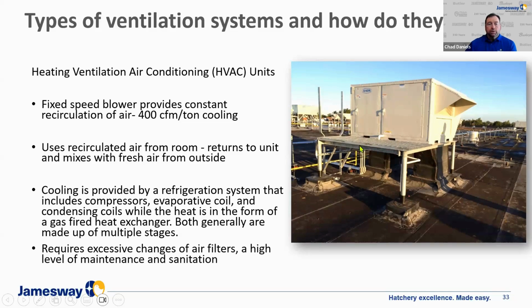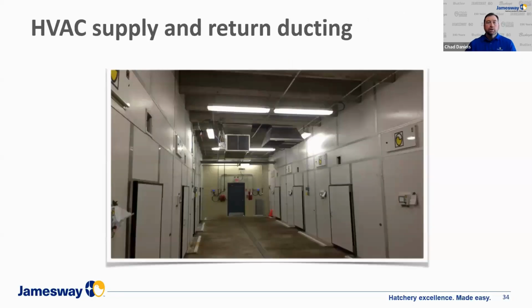So with a system like this, we see it requires excessive changes of air filters. It has a high level of maintenance. It also has a high level of sanitation, because some of the dirtiest air we have in the hatchery comes from our egg pack. And anytime we're pulling that air from the hatchery back up into units, we're going to see some excessive amounts of contaminants and debris that gets built up into these units. So when you take a look in a typical room, you would see where the ducting is here in the picture, and the supply air simply comes out of the discharge grill, and the return air comes back up through a filter rack and is pulled back up into the unit.